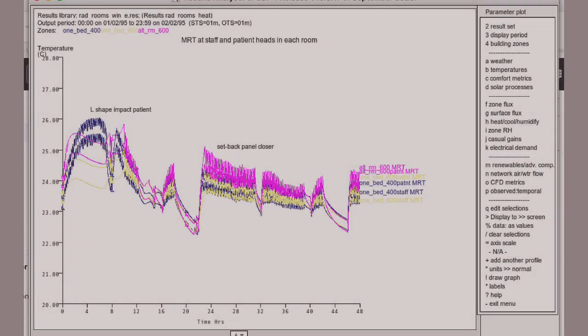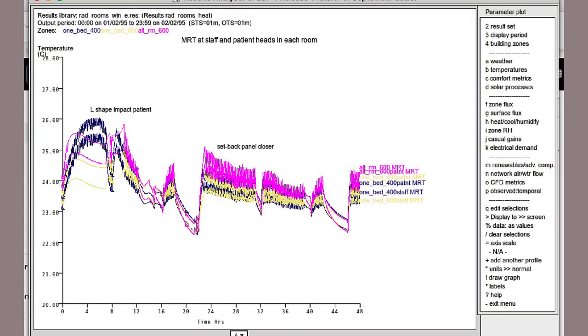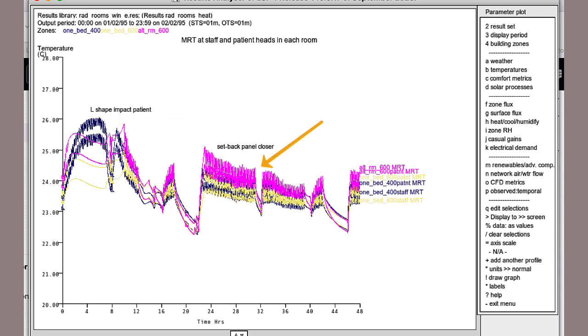And in terms of surface and air temperatures, there's essentially no differences. What does change is the mean radiant temperature calculated at the sensors located at the occupant head positions. The black lines in the figure indicate an initial one or two degrees C increment. By the time we get to the second day, those are about a degree warmer simply due to the position of that panel.